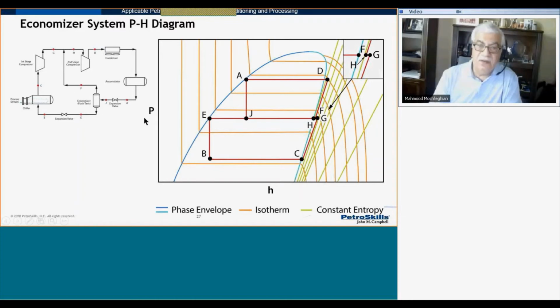For hand calculation, I can take this discharge pressure, which I know, multiplied by suction pressure of this first stage, take the square root of it. That gives me a value for interstage pressure. By doing this, I get equal compression ratio for stage 1 and stage 2. And the power requirement is close to minimum. Not exact minimum, but very close to minimum. So for hand calculation, I would prefer to do that. Take the pressure here, take the pressure here, multiply them together, take the square root, and that gives me intermediate pressure. For our case, the pressure here about 206 psi for compressor. For chiller, about 36. If I multiply them together, take the square root, probably would be 86 psi intermediate pressure.